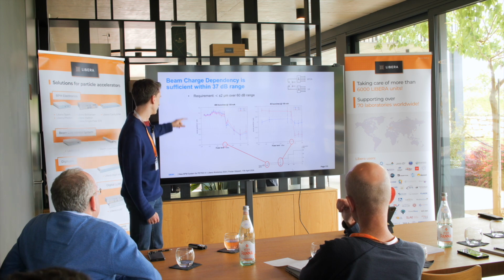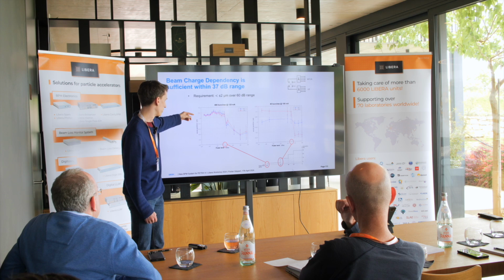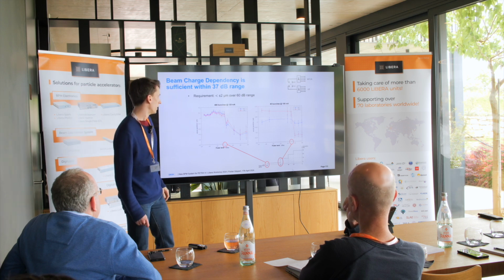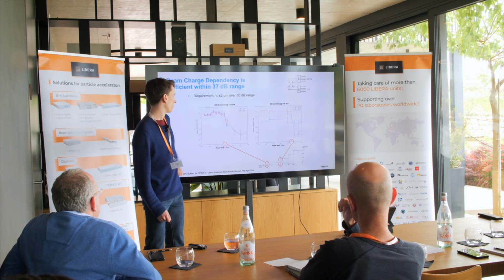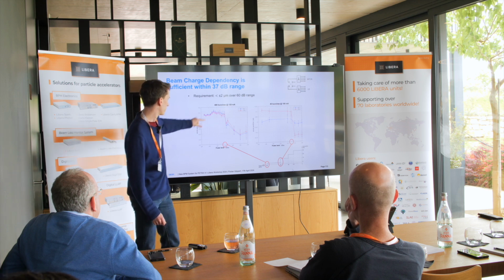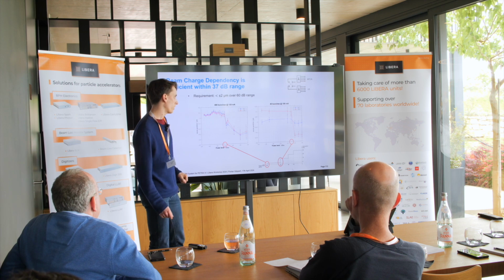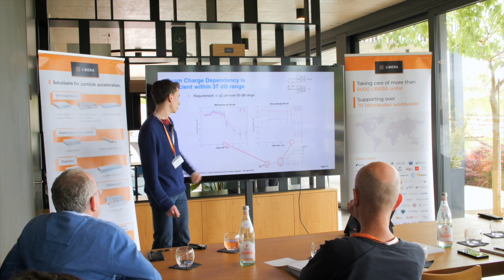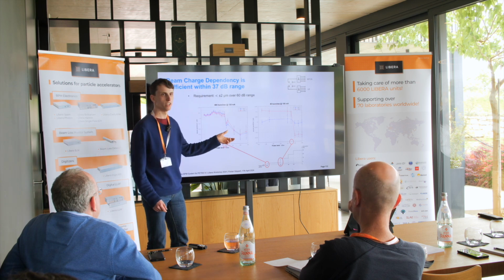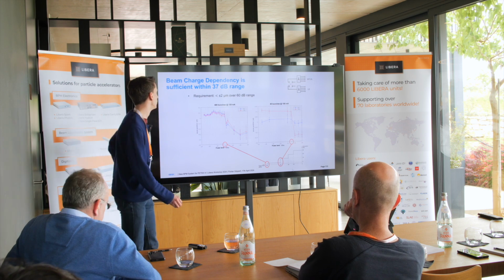And to see also that it is well below micrometers. So here it is 0.1 and goes down to minus 0.3, and similar dimensions on the other side. One thing that is noticeable are the jumps in the data here, which can be related to the gain scheme I mentioned before, because these are the power levels where it's actually switching the attenuation and thus leading to this behavior.